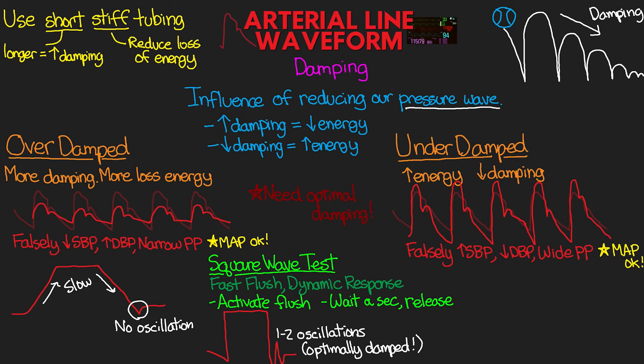If our system has too little damping or is underdamped, we'd expect an exaggerated waveform. Once again, this has an effect on our square wave test. The upstroke and downstroke are going to be quick as we expect, but we are going to see additional oscillations while it's trying to return to baseline. Think of having too much energy — the ball will be bouncing more than expected until that energy is lost. So if we have more than two oscillations, this is an indication that we have underdamping, and we're going to need to troubleshoot that arterial line and then repeat this test.